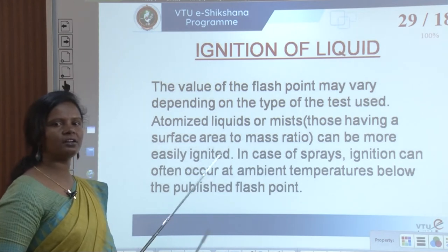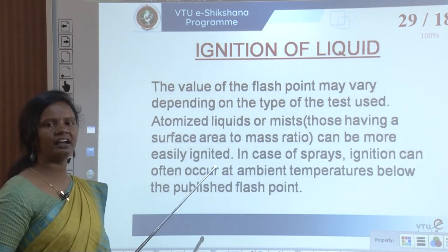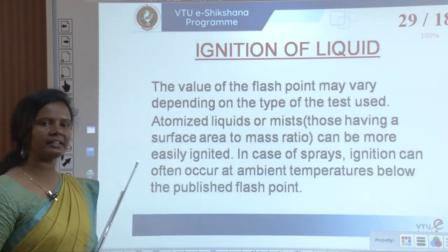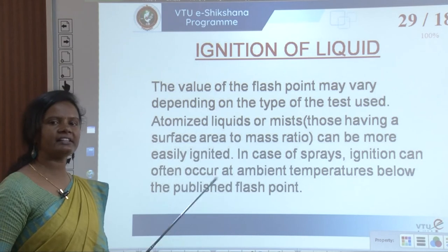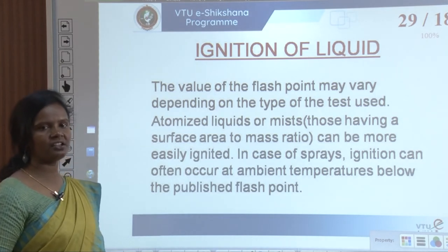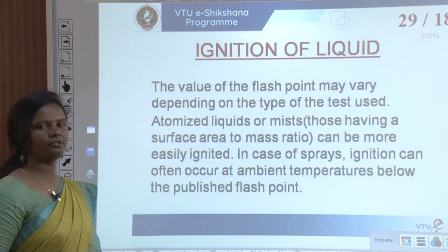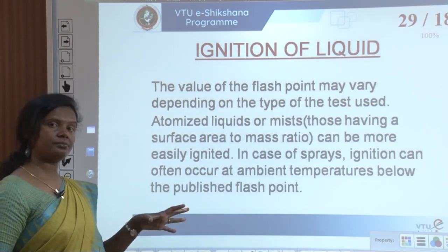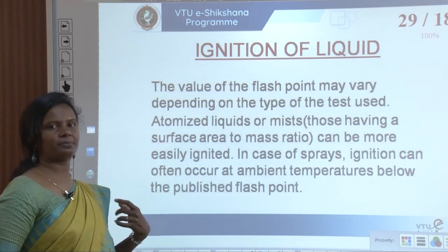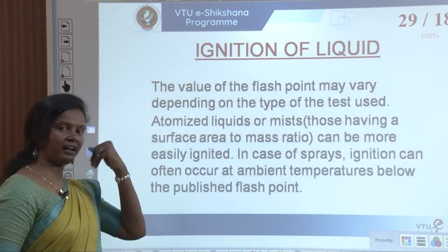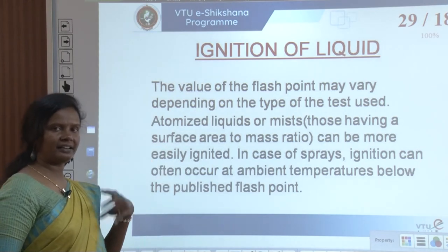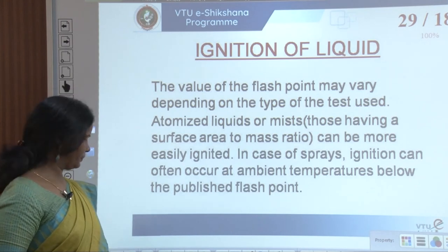Atomized liquids or mists, those having a high surface area to mass ratio, can be more easily ignited. In case of sprays, ignition often occurs at ambient temperatures below the published flash point. In case of spray, ignition can happen even at the ambient temperature, which is below the published flash point. Flash point would be higher for that liquid, but since it is a spray, it can happen at lower temperatures also.